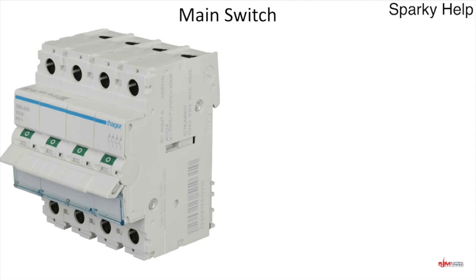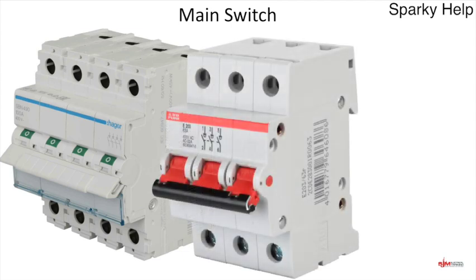Where would you want to use a four-pole? Where you definitely have to use a four-pole isolator as a main switch is a three-phase and neutral TT installation. The regulations state that in a TT installation, you must break all live conductors — and remember, this includes the neutral. But you could equally use these in any other three-phase and neutral installation; it's just not a regulation requirement. In all other types of three-phase installation, you could get away with just a three-pole switch.